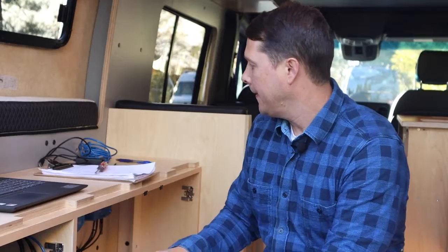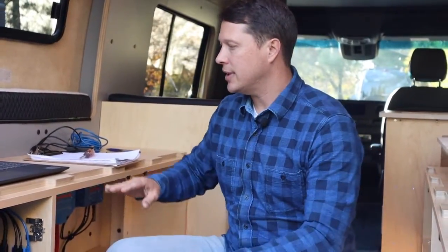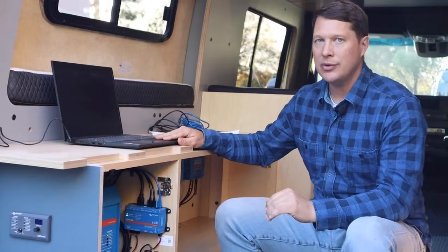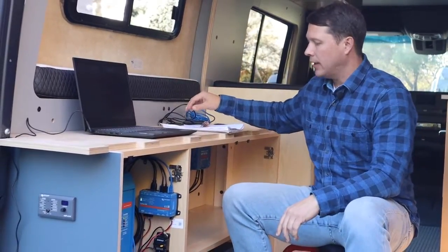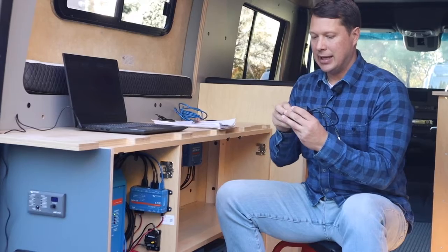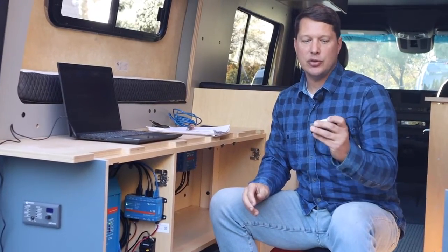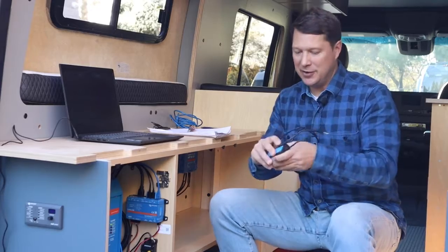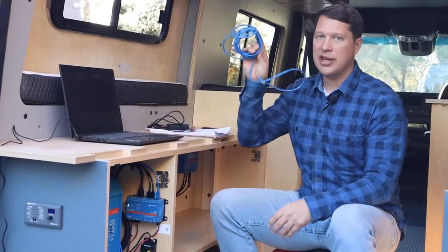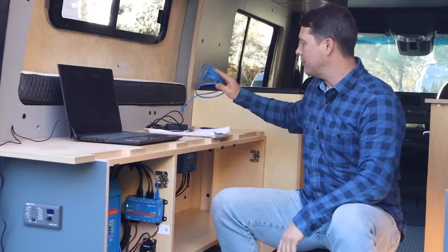All right, here comes the fun part, which is programming the Multi-Plus inverter. It's actually not the fun part, it's the hardest part because you need a couple special pieces of equipment to do it, but it is really important. If it wasn't pre-programmed when it was sent to you, then it needs to be programmed when you start the system up. So what we're gonna need in order to do this is a laptop that's running Windows, because we'll have to download some software. We're going to also need this VE bus to USB dongle, if you will, and then an RJ45 cable, which will plug into the Multi-Plus.